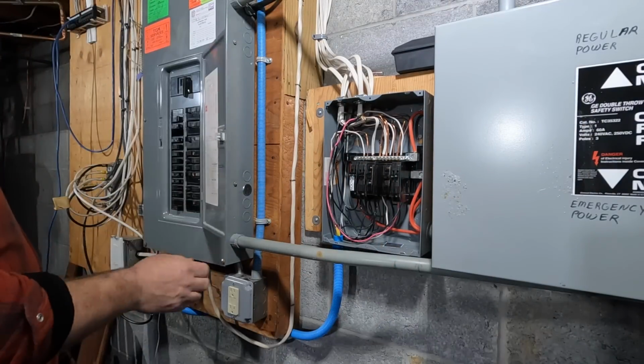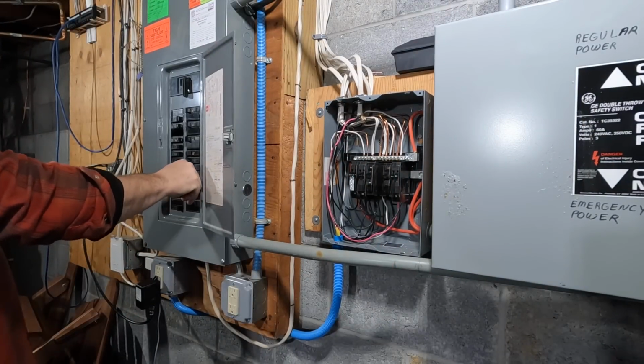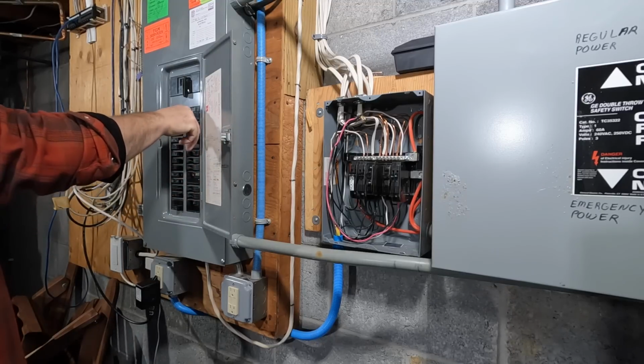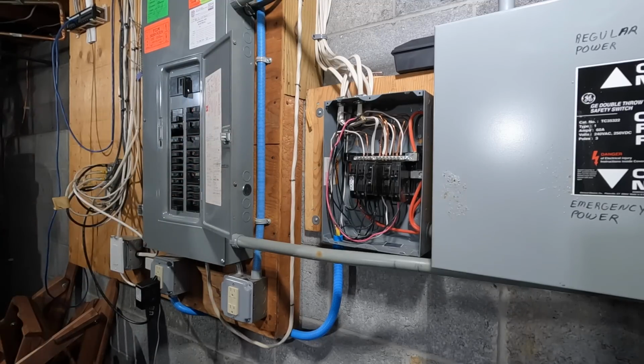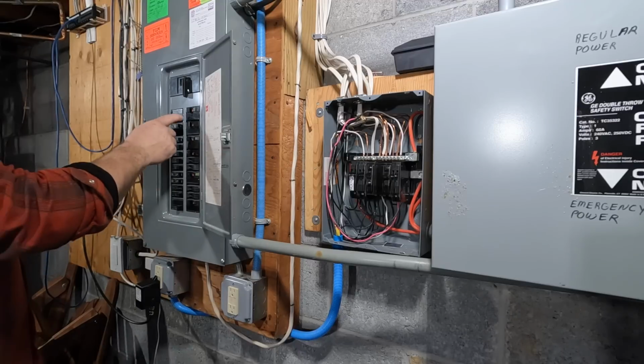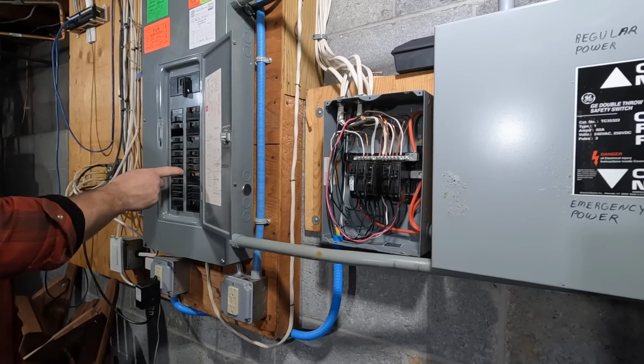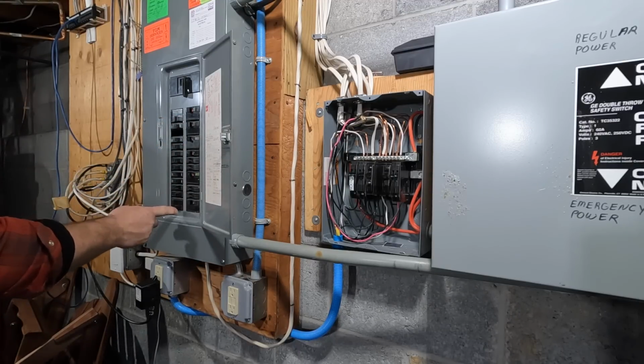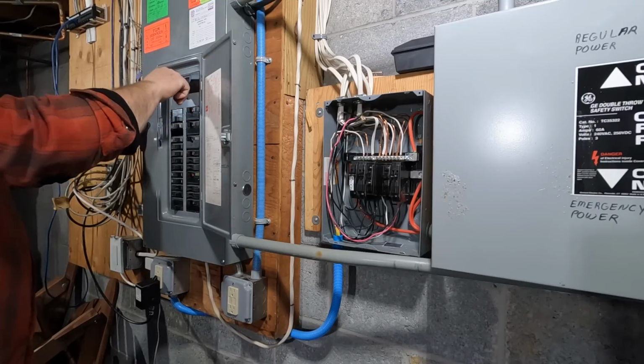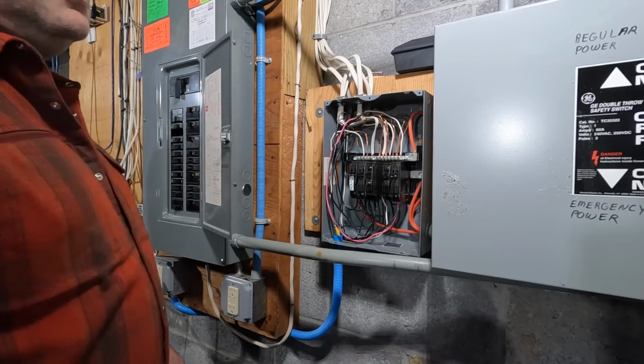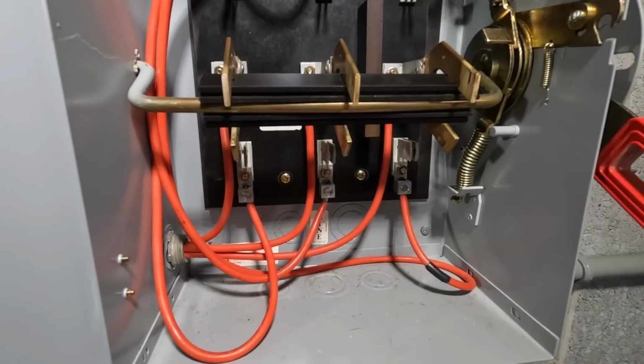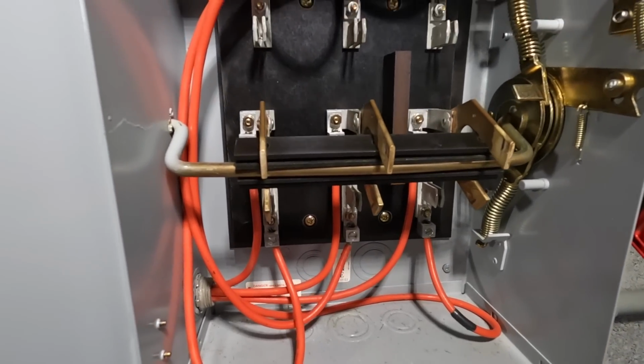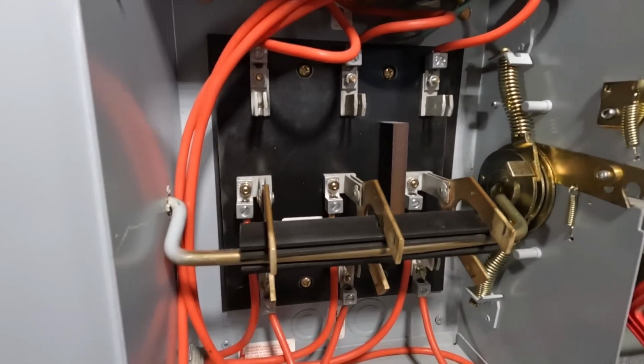We always want to shed the load first, and so this panel on the side here, obviously they relocated a bunch of those circuits to connect to the portable generator, which is what you see on the side. By the way, what is regular power versus emergency power? That's how you can tell for sure that an amateur put this together. Wait till you see the wiring. All orange conductors and nothing identified as a neutral or a ground. Obviously, this is all bootleg right here.